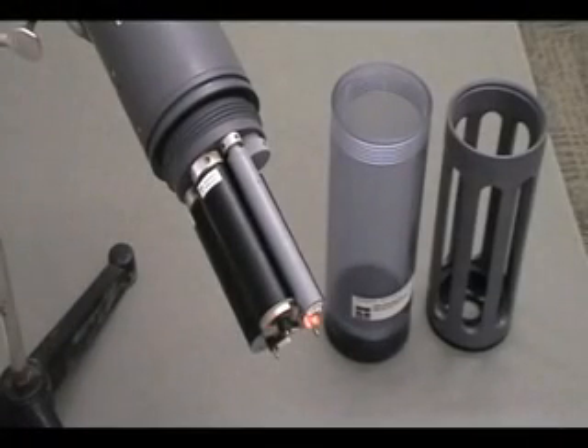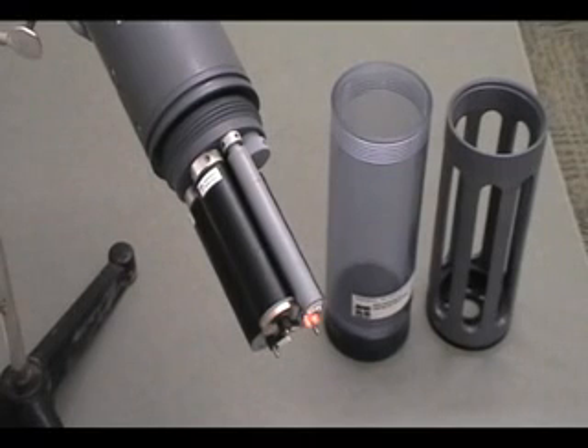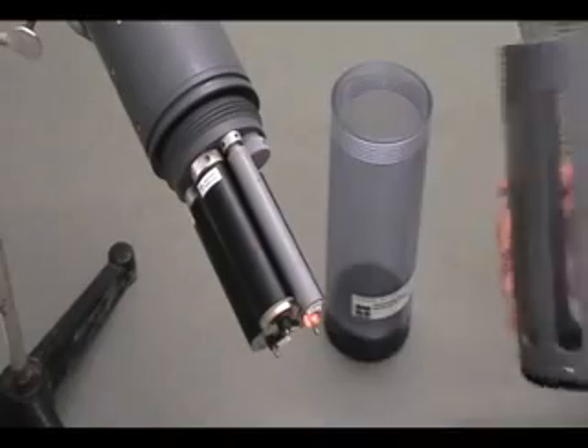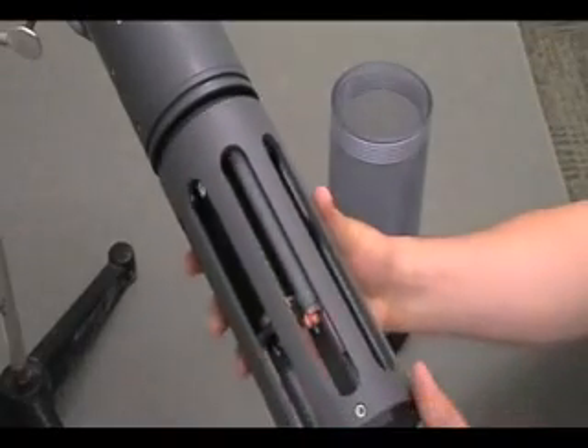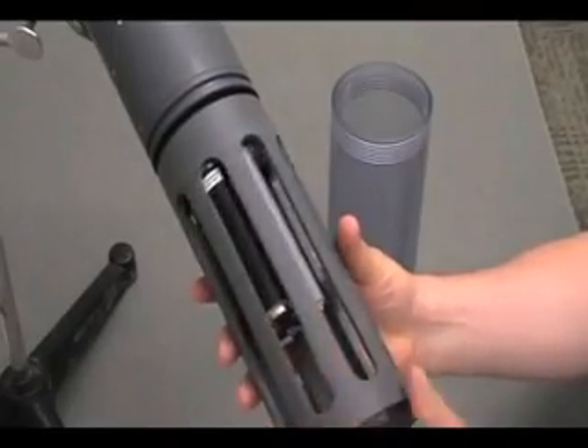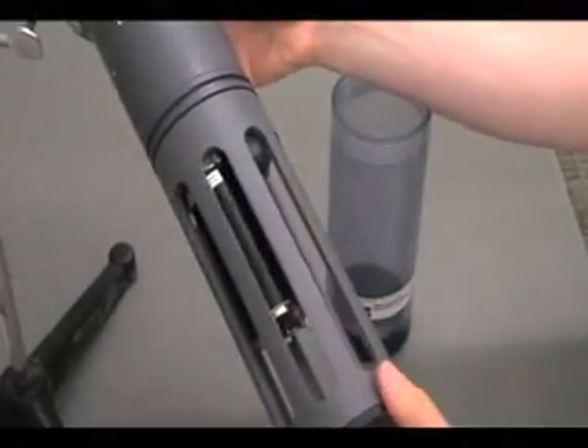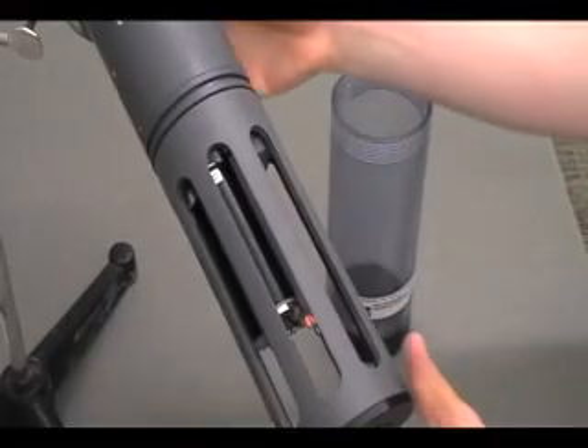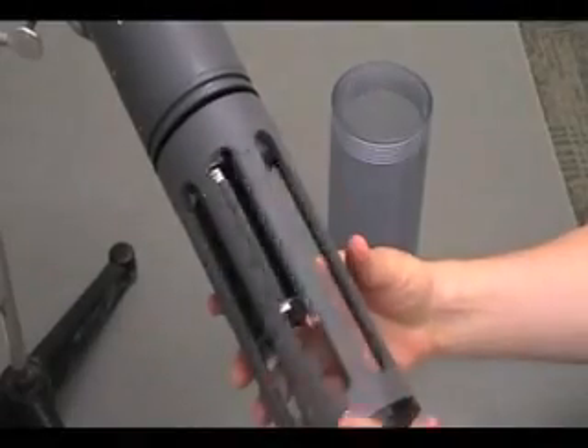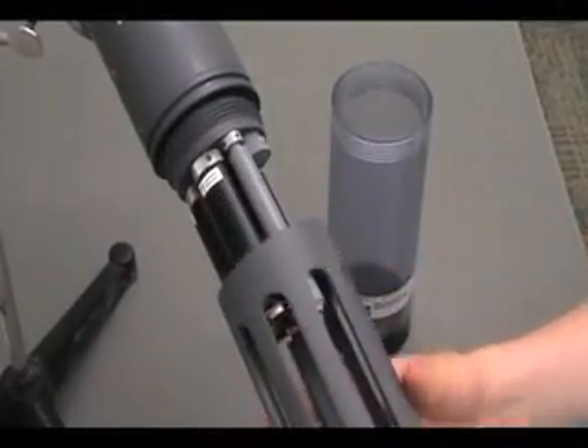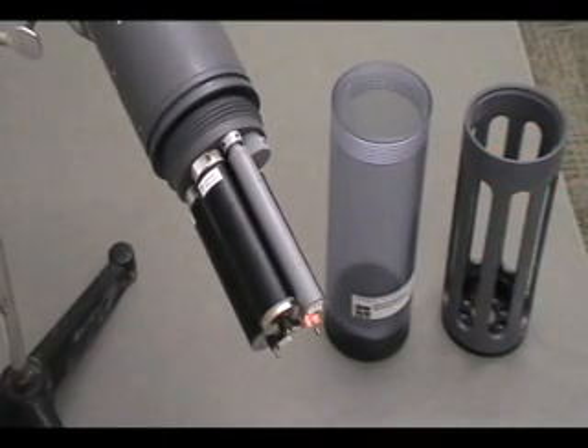Installing the probe guard or calibration cup. The probe guard protects the sensors during deployment and allows water to flow over the sensors. Once all the probes are correctly installed and calibrated, screw the guard onto the sonde by aligning the threads and turning clockwise until the probe guard is securely attached. The calibration cup is used during sensor calibration and for long-term storage when the sonde is not in use. It is a solid plastic cup. The calibration cup is installed in exactly the same way as the probe guard.